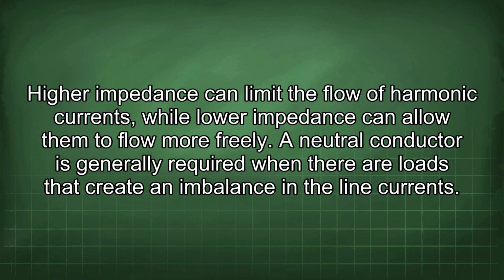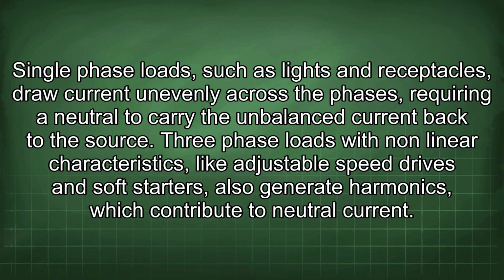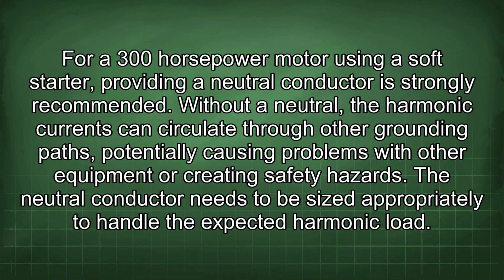A neutral conductor is generally required when there are loads that create an imbalance in the line currents. Single-phase loads, such as lights and receptacles, draw current unevenly across the phases, requiring a neutral to carry the unbalanced current back to the source. Three-phase loads with nonlinear characteristics, like adjustable speed drives and soft starters, also generate harmonics, which contribute to neutral current. For a 300 horsepower motor using a soft starter, providing a neutral conductor is strongly recommended. Without a neutral, the harmonic currents can circulate through other grounding paths, potentially causing problems with other equipment or creating safety hazards. The neutral conductor needs to be sized appropriately to handle the expected harmonic load.